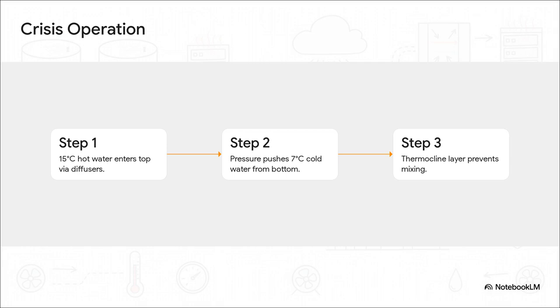So the power fails, the chillers stop, but the server rooms are still pumping out hot water, typically around 15 degrees Celsius. Step 1. This hot water is gently, and I mean very gently, pushed into the very top of the tank. Engineers use these specially designed pipes called diffusers to make absolutely sure the water enters smoothly without creating any vortexes or turbulence whatsoever. Step 2. As that hot water fills the top, its downward pressure perfectly pushes the stored, still 7 degrees Celsius cold water out from the very bottom, sending it straight back to the server rooms.